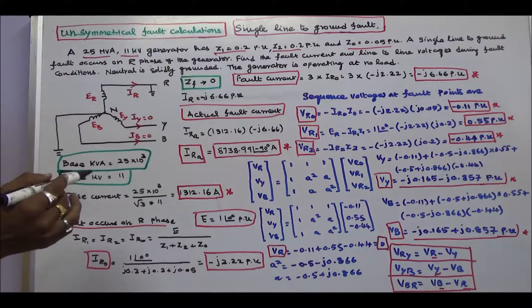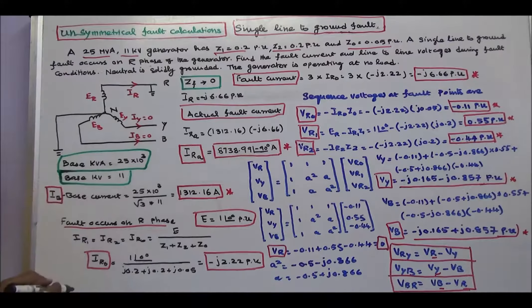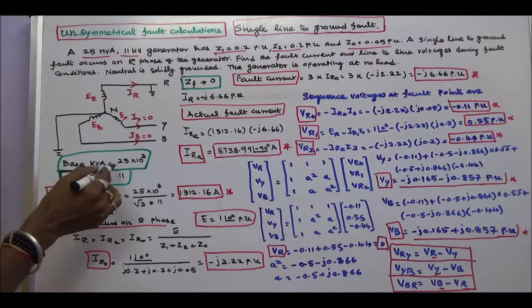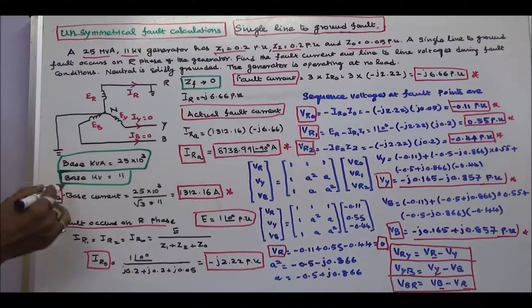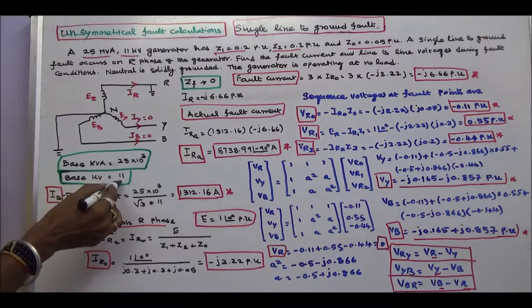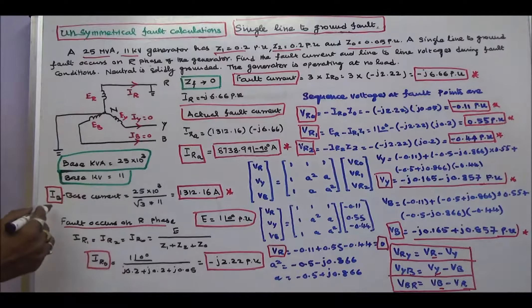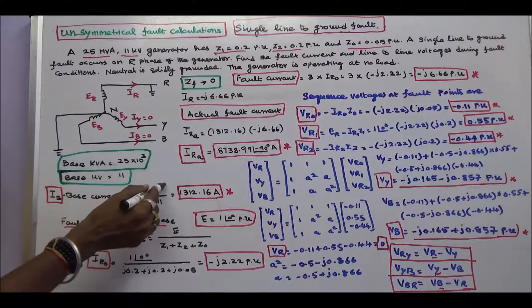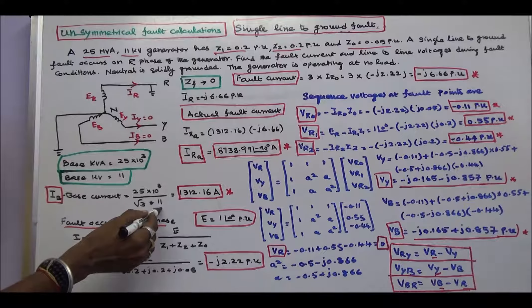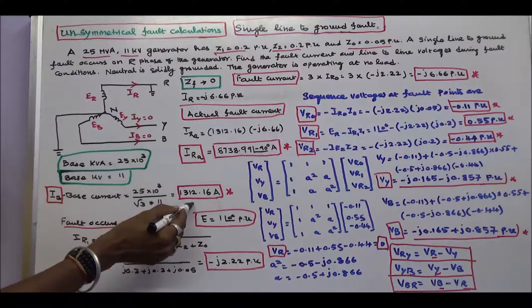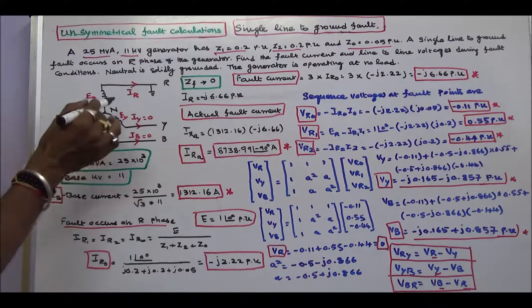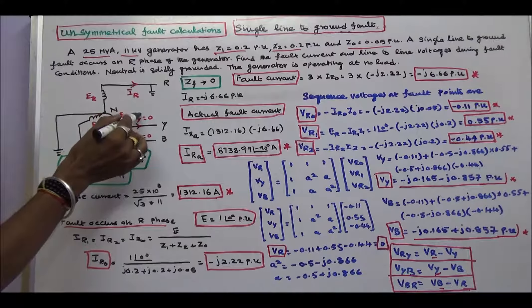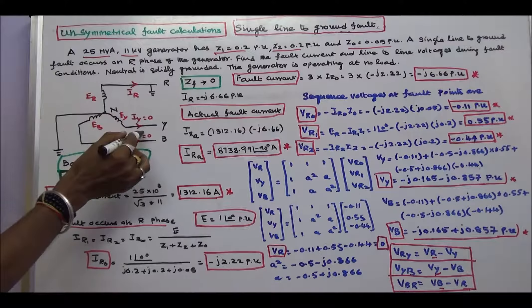First step: choose base KVA equal to 25 into 10 power 3, and base KV equal to 11. Now the base current is equal to 25 into 10 power 3 divided by root 3 into 11, which equals 1312.16 amps. Here the fault current conditions are: IR is the fault current, IY equals 0, and IB equals 0.